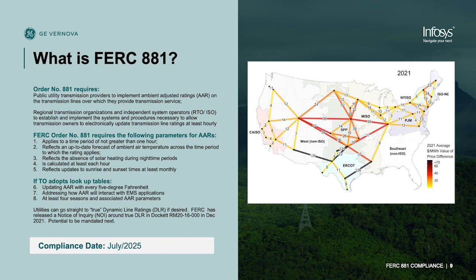So some examples are, traditionally a summer-based rating might be based on a 40 C ambient temperature with some known wind speeds and directions. And then your winter would be based on 10 degrees Celsius with known wind speed and directions. So really the traditional rating systems don't take into account any of the weather-based conditions, changes in ambient temperature or changes in the wind speed and direction. So really they're kind of a conservative rating set that limits the overall capacity on the transmission system.